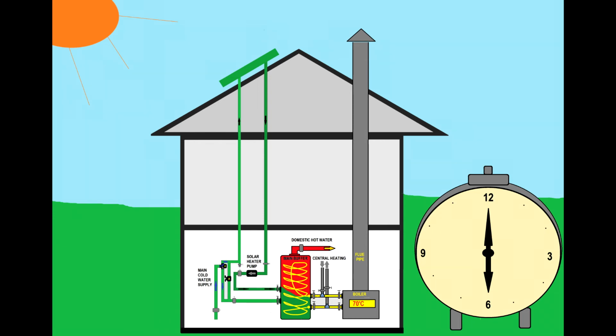You have to be very careful how you design your control philosophy at this point. So exactly as I said, if you run the ring circuit, the hot water from the main buffer will reach the solar heater panel's heat exchanger, and because outside it's very cold and the water is 70 degrees, the energy from the solar heater panel will migrate into the atmosphere. That will act like a cooler, and the boiler will work harder to achieve the temperature in the main buffer, wasting a lot of energy because the solar heater panel will constantly try to cool the main buffer.